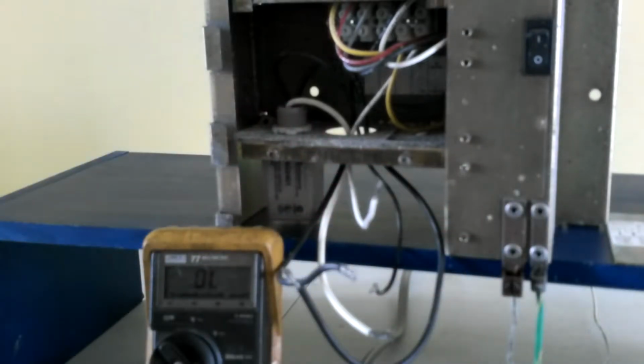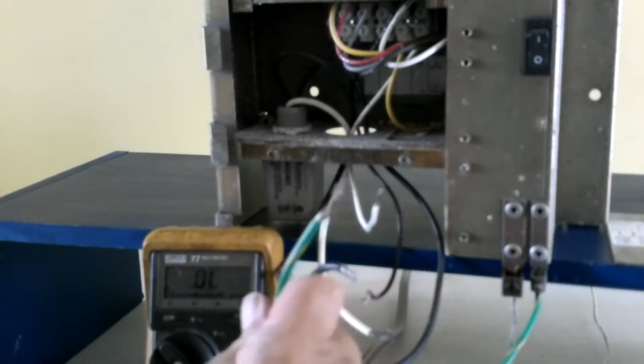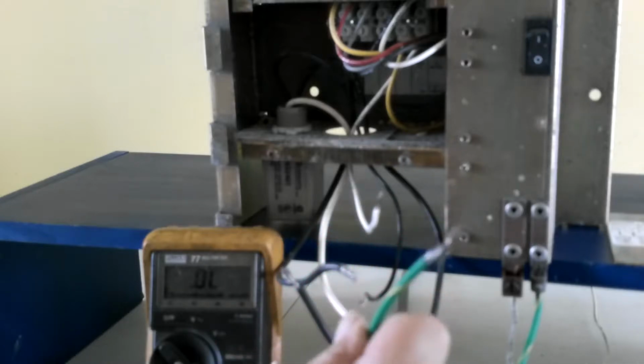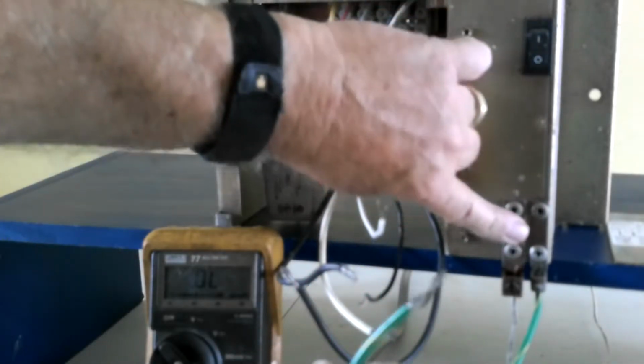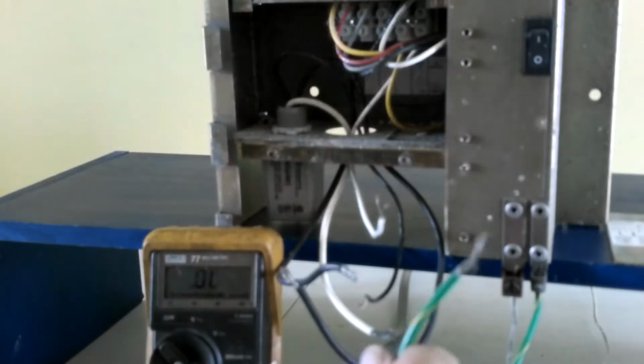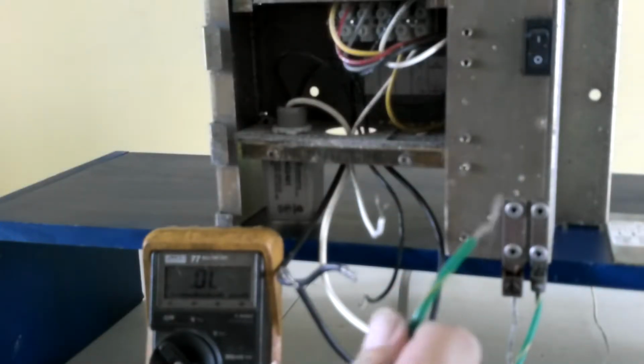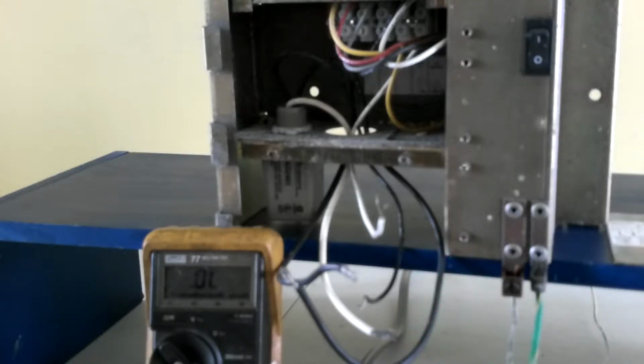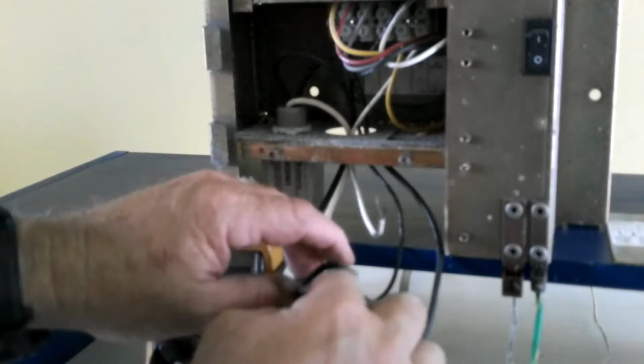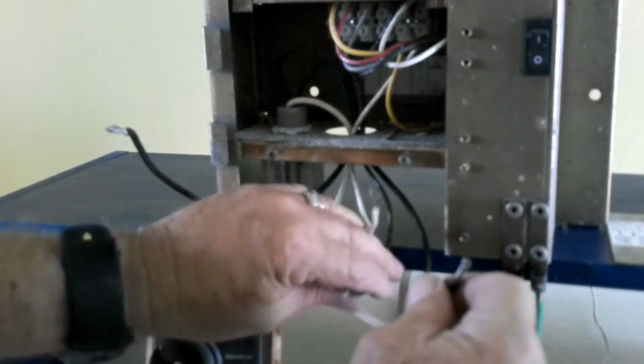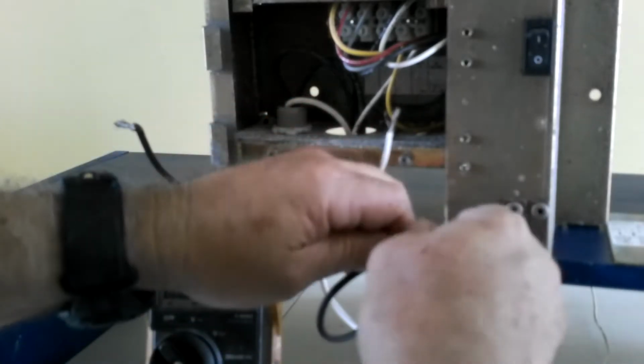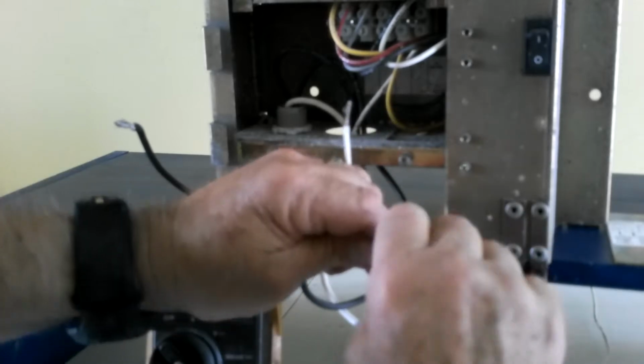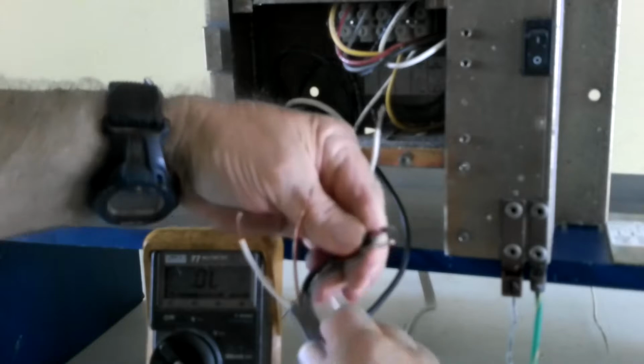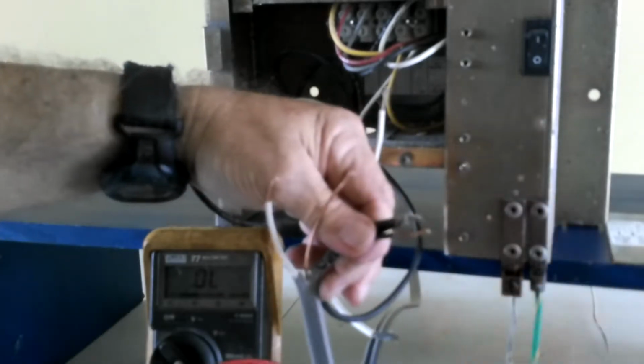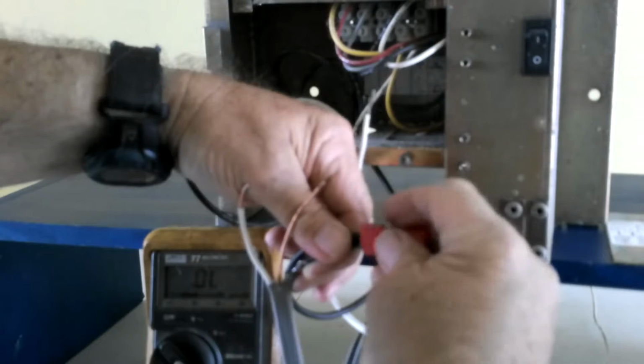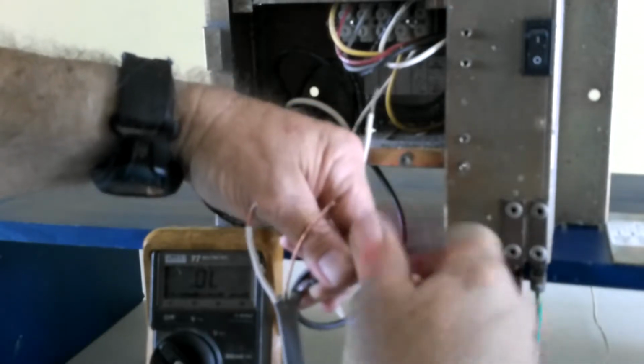The next thing you want to find is the wire that is connected, or a wire connected to the earth-ground connection, which is going to a ground rod, because that becomes extremely important when you're putting this together. Now the first step is to take one of the black wires, the hot black wire from the transformer, twist those together, and then connect them to the black wire that is in your power supply, coming from your power source, which is your hot lead.